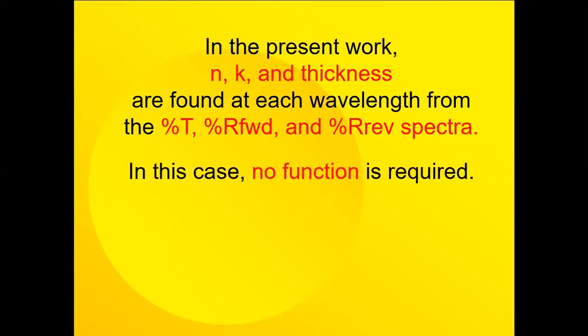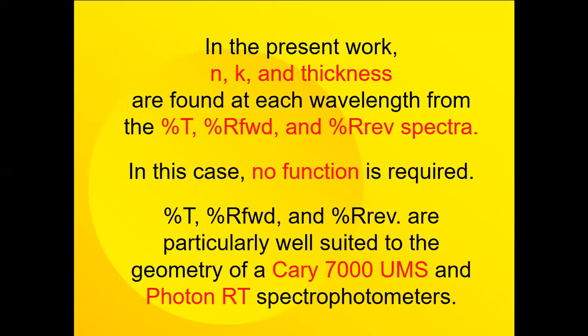In this case, there are no functions used. So the percent T, percent R forward or reverse are particularly well suited to the geometry of the Cary 7000 with the universal measuring system and the Photon RT spectrophotometers made in Europe.